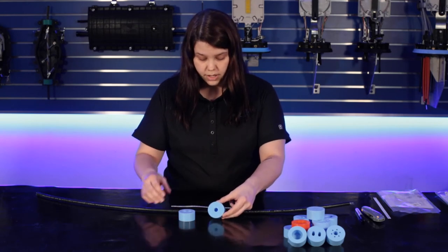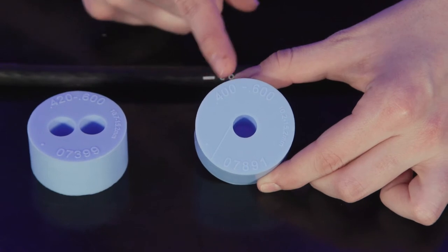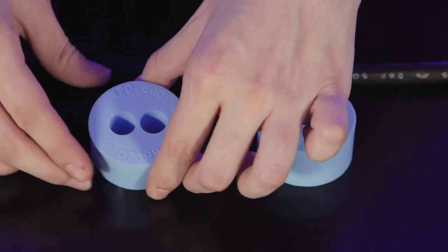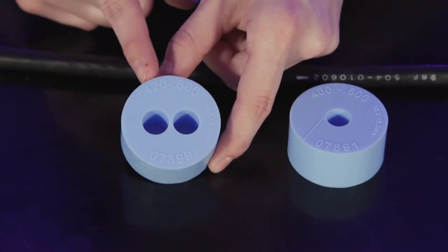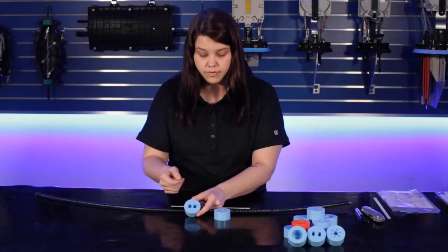My cable is 0.48 inches. The one-hole grommet has a range from 0.4 to 0.6. It's right on the grommet so you can never forget. The two-hole grommet has a range between 0.42 to 0.6. Either one will work for my cable.